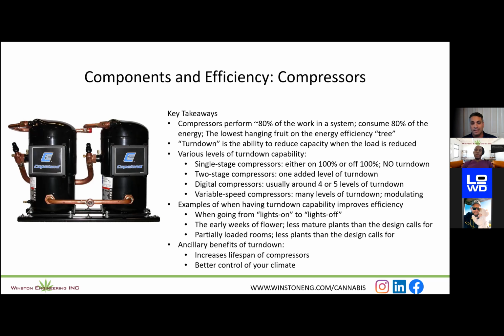And then the ancillary benefit of turning down is it's going to increase the lifespan of that compressor. If you've got 50% of the load in the space and you've got a single stage compressor, it means you're operating at 100%, and that compressor is going to burn up a lot quicker than if it's matching the load precisely. And then again, like I've mentioned a few times, better control of your climate.